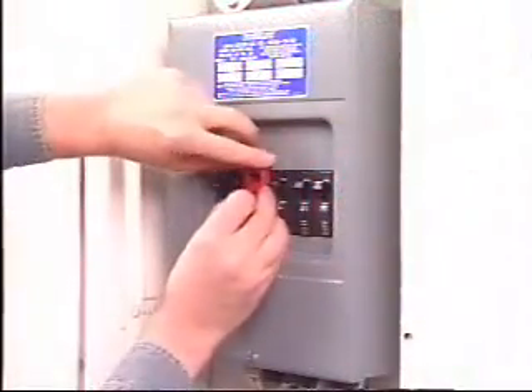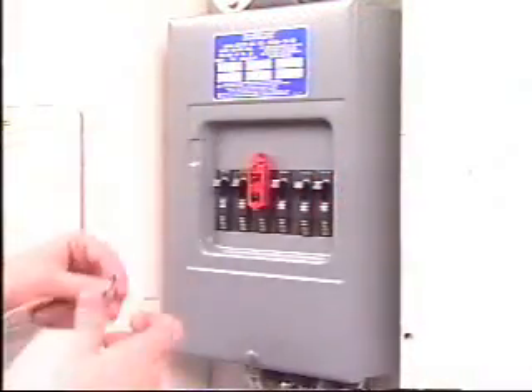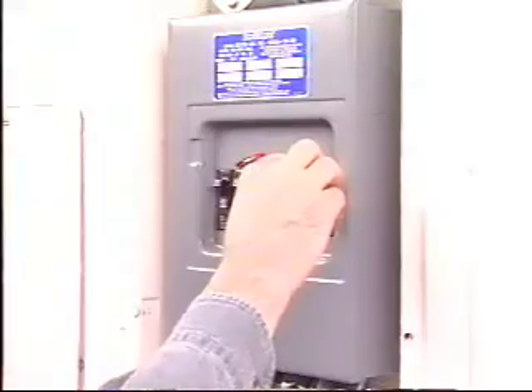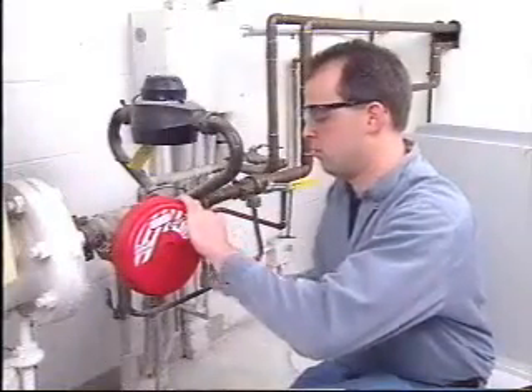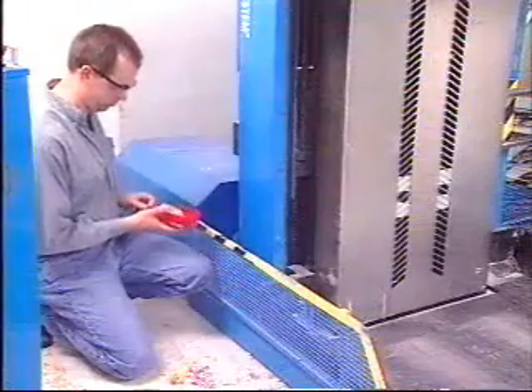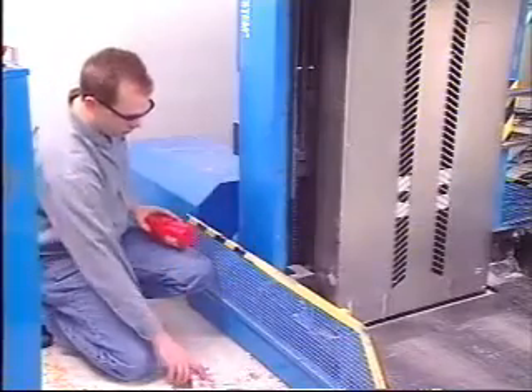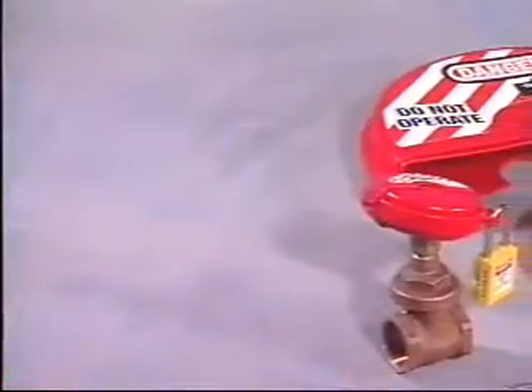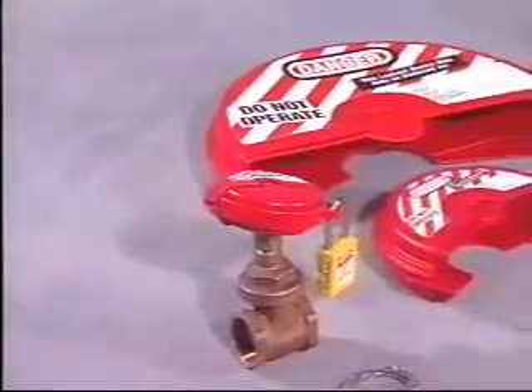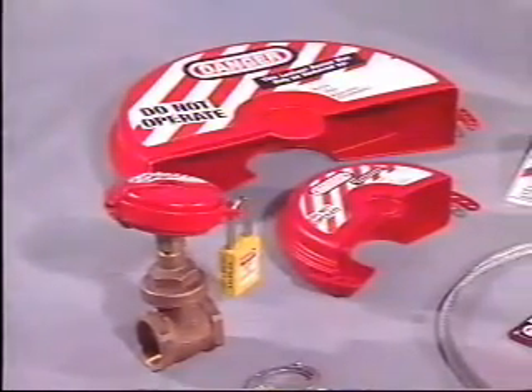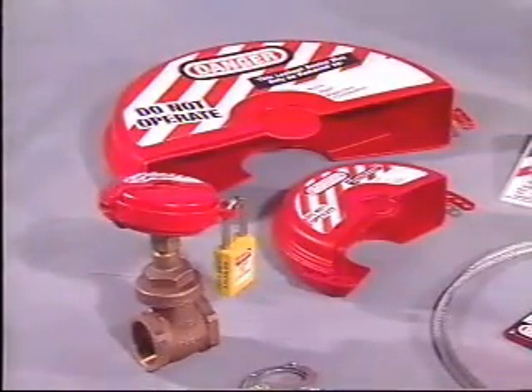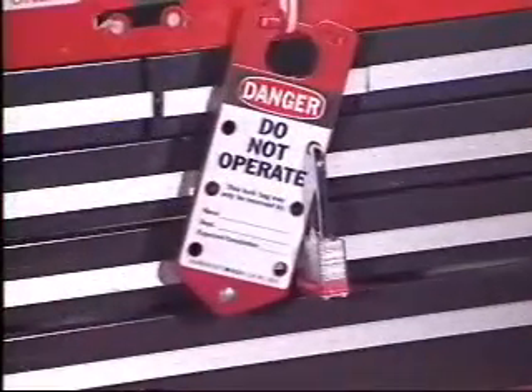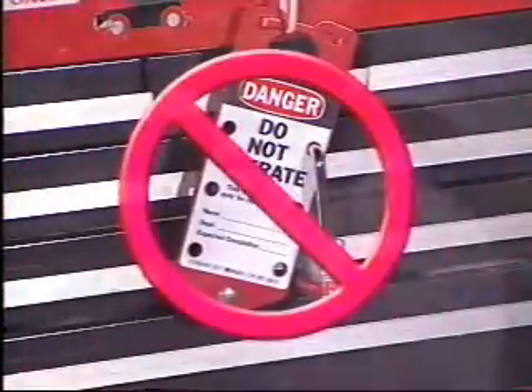Every power source has its own procedure for lockout. It may mean locking out a circuit breaker, locking a valve shut, or using a plug lockout, to name just a few. LockOutTagOut locks are provided by your employer. They must be used only for lockout purposes. Never use them to lock a toolbox or storage area.